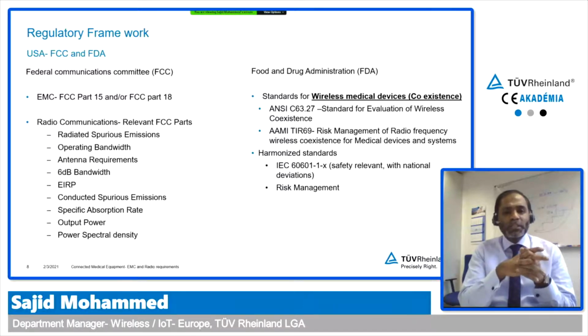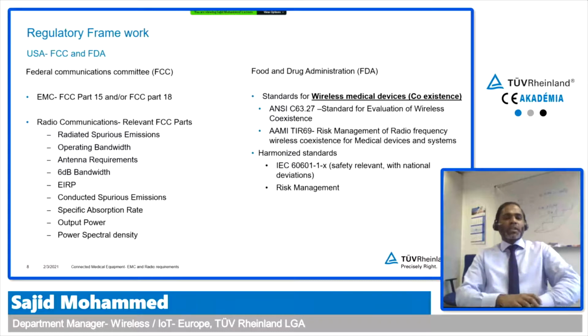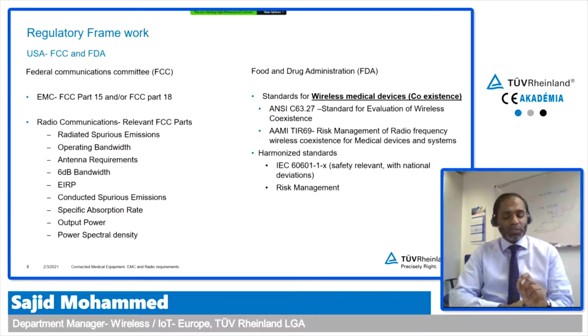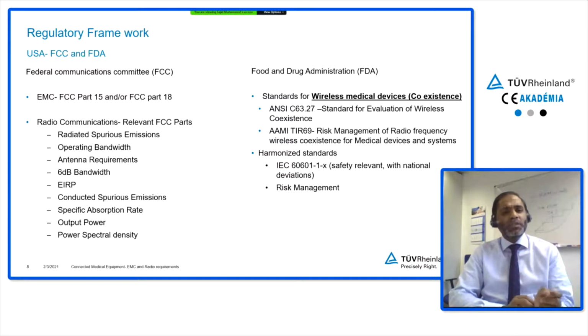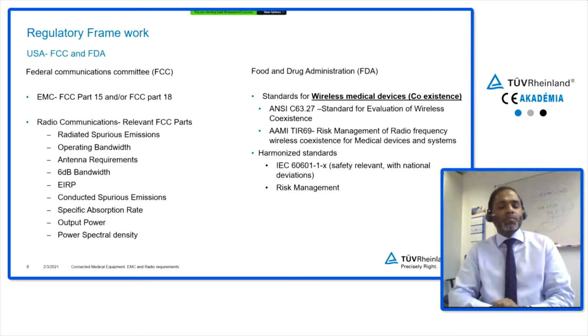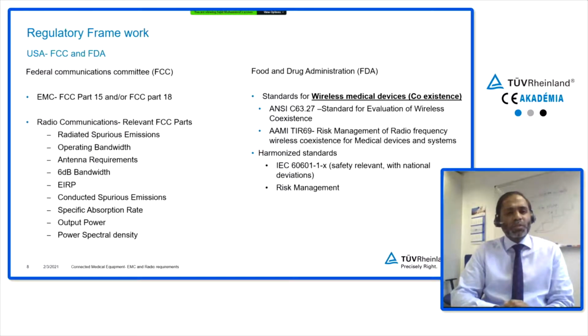These rules lay down individual test requirements like radiated spurious emissions, operating bandwidth, antenna requirements, 6 dB bandwidth, EIRP, spectral density, and apart from that, specific absorption rate measurements, so-called SAR. The medical part of the device is regulated by FDA, which has also put in requirements for wireless medical device coexistence.